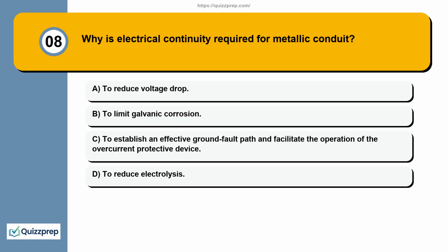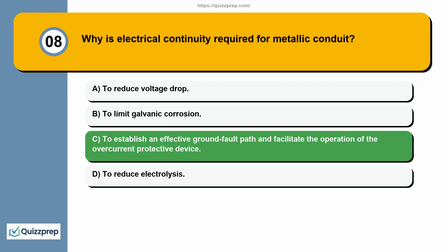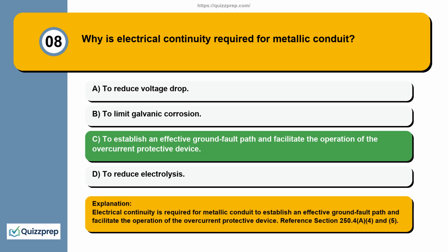Question 8. Why is electrical continuity required for metallic conduit? To reduce voltage drop, to limit galvanic corrosion, to establish an effective ground fault path and facilitate the operation of the overcurrent protective device, to reduce electrolysis. Electrical continuity is required for metallic conduit to establish an effective ground fault path and facilitate the operation of the overcurrent protective device. Reference section 250.4(A)(4) and (5).